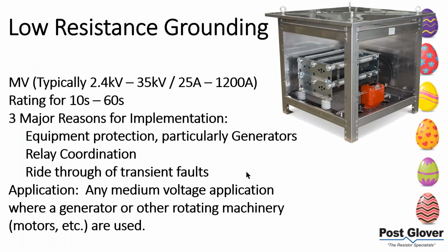Move on from there. There are two different types of resistance grounding: low resistance grounding and high resistance grounding. Let's talk about low resistance grounding first. Typically, it's almost always at medium voltage, 2.4 to 35 kV. Really, the sweet spot is between 5 kV and 15 kV. You could actually go higher than that if you'd like, but it's most common there. We see the vast majority of our applications are 5 and 15 kV class at least. Currents range from 25 amps to 1200 amps. You could go higher than that if you have a lot of imbalance or some large application where you need a higher current, but it's not that typical. Your sweet spot at those medium voltage ranges could be 200 to 400.